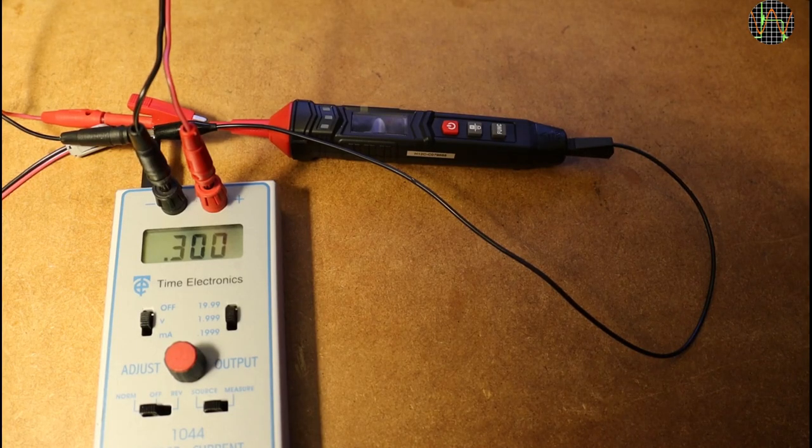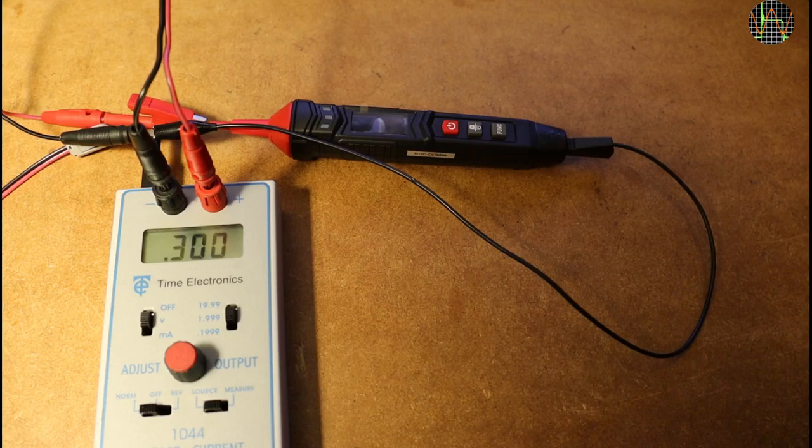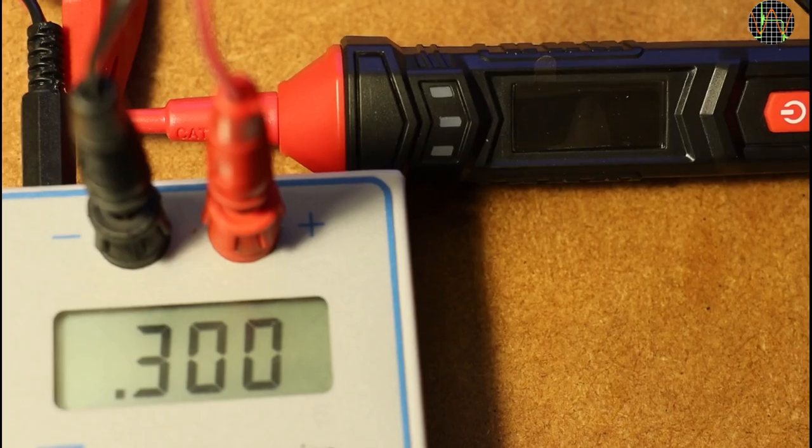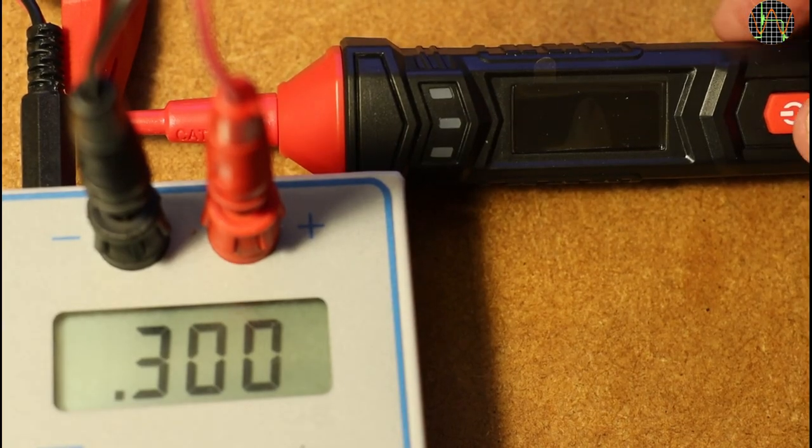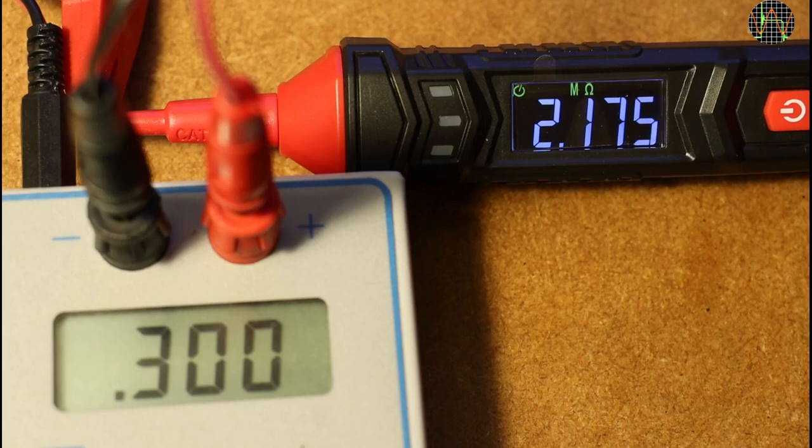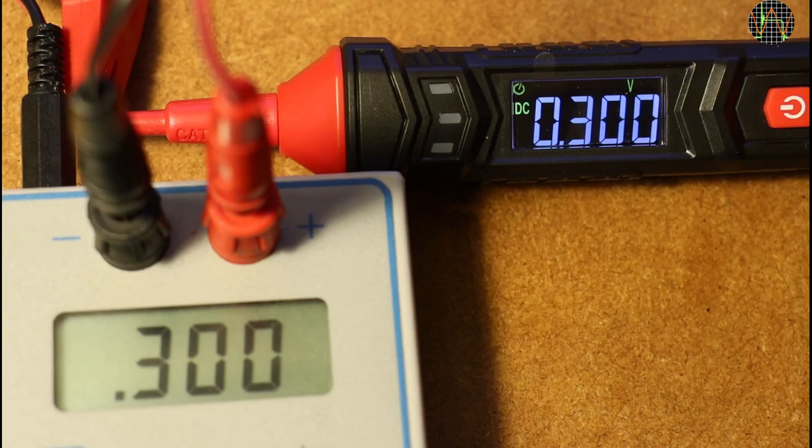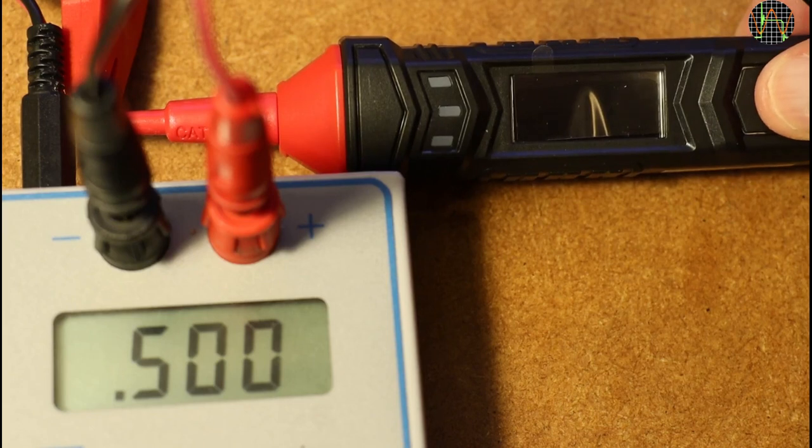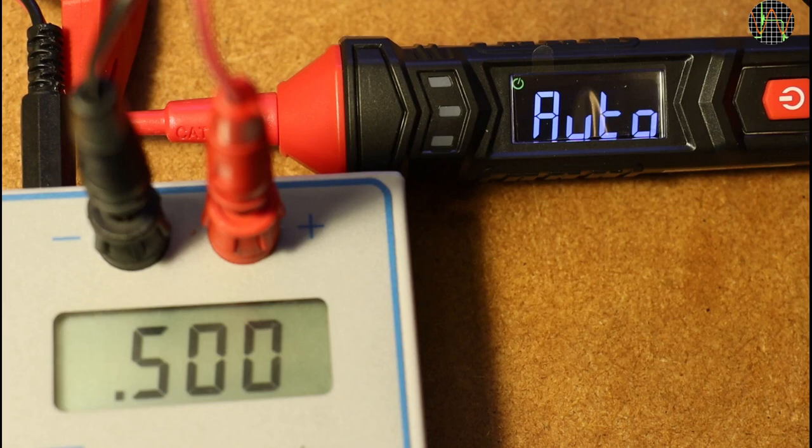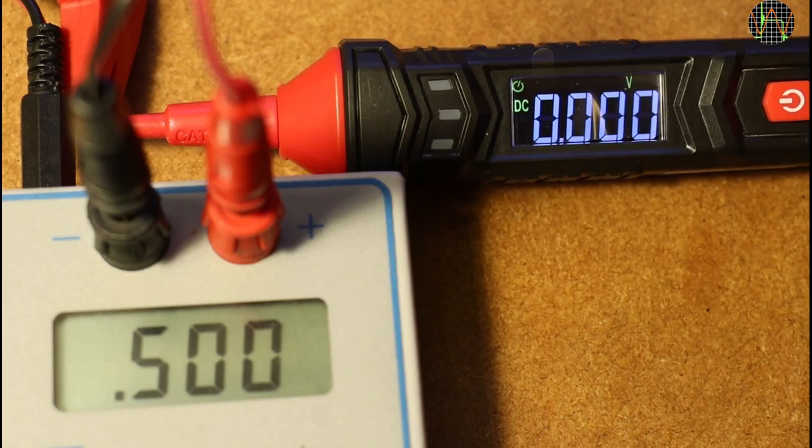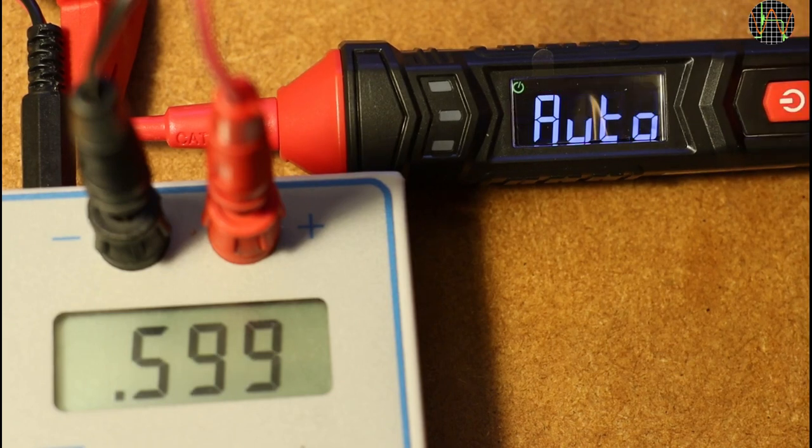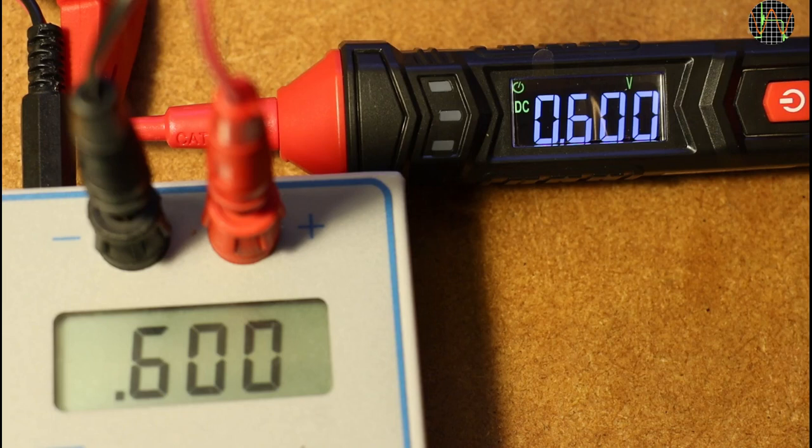To demonstrate the behaviour at low DC voltages, I used this calibrator connected to the ST120. This calibrator can generate very accurate DC voltages or currents. The calibrator is producing a DC voltage of 300mV and when the meter is connected, its AUTO mode recognises that as a resistance of just over 2MΩ. But if I switch manually to DCV mode, it has no problem measuring 300mV exactly. Per chance I found that 500mV is the value where AUTO mode is stuck not doing anything but again, switching manually to DCV shows the correct value. At 600mV, AUTO mode does recognise the voltage and switches to DCV itself.